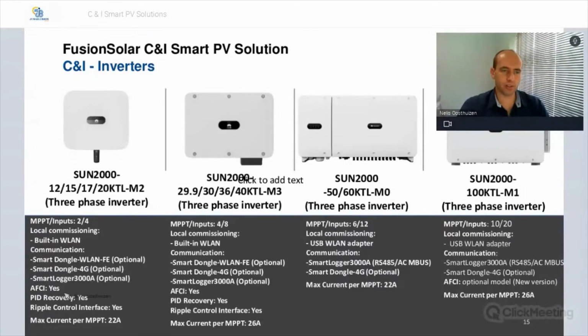The smaller range of inverters has got built-in AFCI. AFCI is arc fault current interruption. It's got built-in PID recovery, and then it also supports ripple control interface. The maximum current per MPPT is 22 amps. So please note that this maximum current, 22 amp, make sure that when you do your designs and you have 2 strings that's connecting to 1 MPPT, that you are less than this 22 amp.